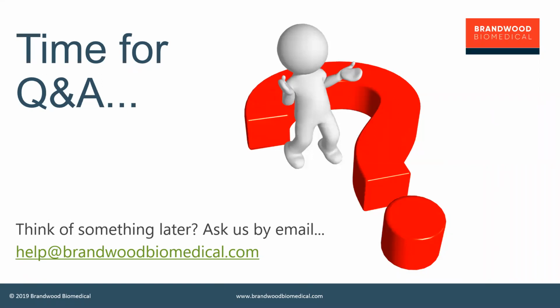Indeed. Emmett from Ireland has asked us, when do we expect Europe to harmonise the new Part 1? Well, Emmett, harmonisation in Europe usually takes about 6 months, and so we're coming up to 6 months since the document was published in August. However, it might be a bit delayed this time because there's a lot of things going on in Europe at the moment with MDR, and that may get in the way. But I think that it won't be too much longer before we see the European harmonised version come out.